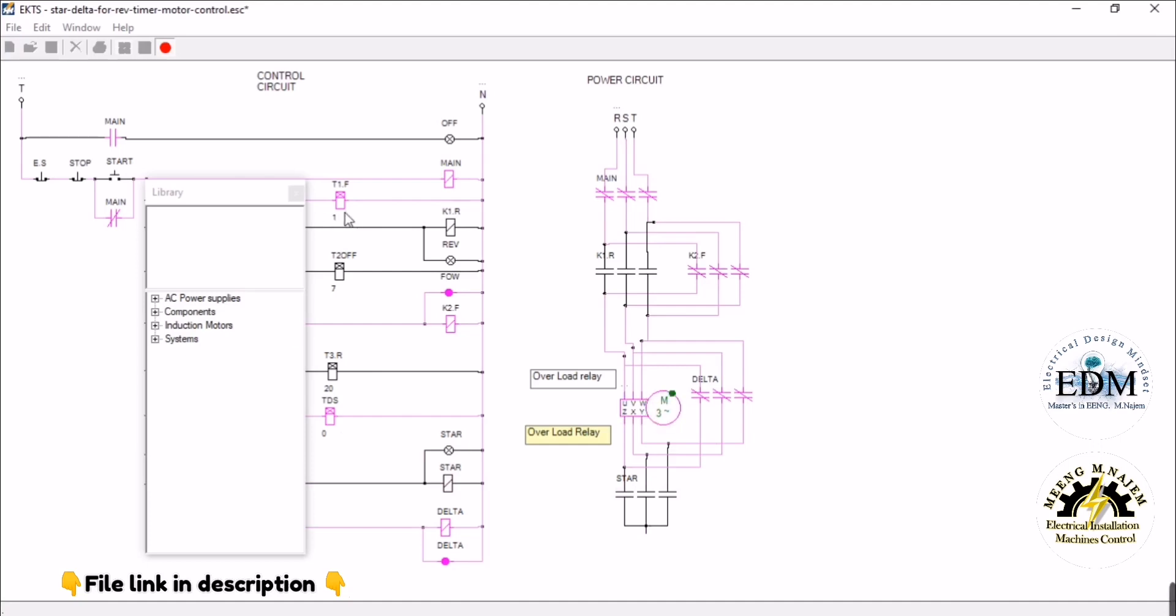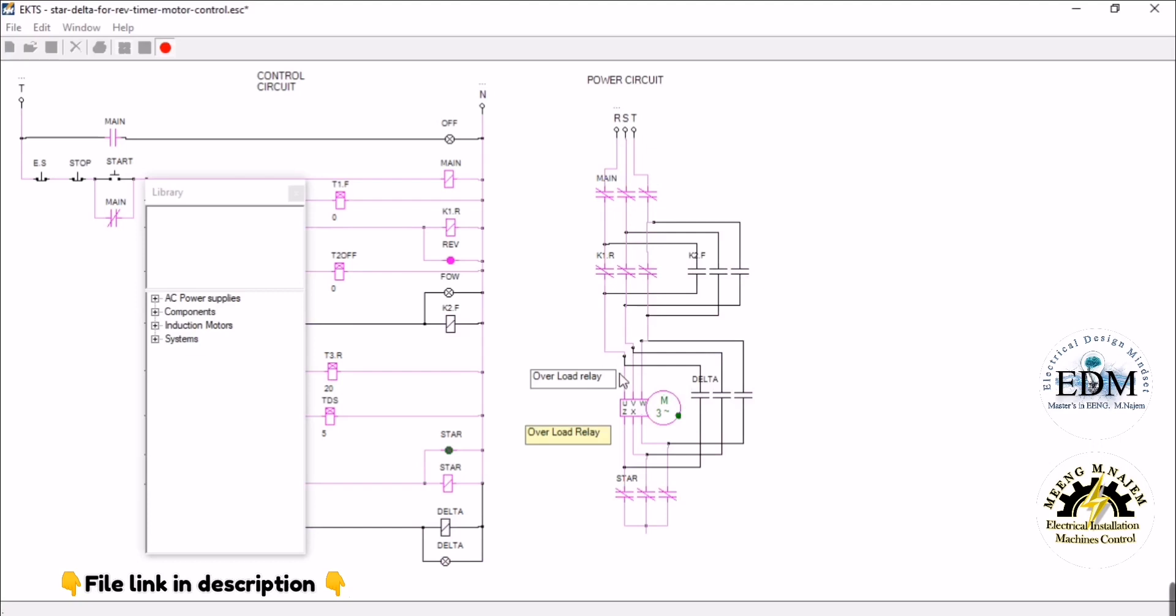When the cycle ends, the motor stops for five seconds, since we can't reverse motor rotation directly as it causes damage. When timer T-off ends, the motor starts running clockwise with star configuration, then after five seconds switches to delta connections.